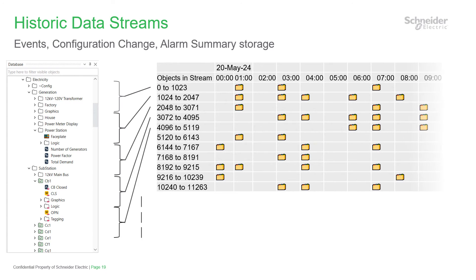Stream setup is important for all but the smallest GeoSCADA systems. Streams apply to the text-based historians such as the events and the alarm summary. The stream size for events gathers event entries for consecutive database items into hourly files. This diagram can help explain this, but do note that the ordering is not by database hierarchy — it's by database item ID. Streams are used to group and separate files in the historian so you don't get files which are too large or too many files, either of which could cause performance issues.